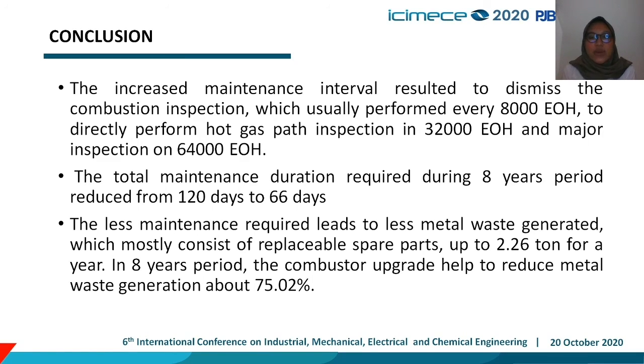The less maintenance required leads to less metal waste generated, which mostly consists of replaceable spare parts, up to 2.26 ton for a year. In an 8 years period, the combustor upgrade helped to reduce metal waste generation by about 75%.